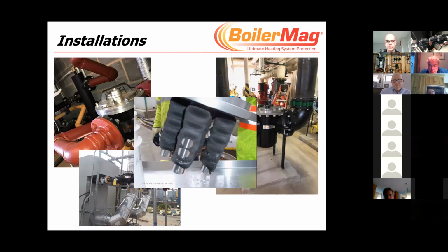We always get the question: how often do you need to clean these? Well, it depends on the system, and how bad the system is. I can give you an example. I installed the BoilerMag on my new boiler system - I'd taken it back to the studs, all new copper piping, no cast iron radiators. I opened mine up after about a month and the magnet was packed. I opened it again after another month and had about half the amount. After about 6 months, I'd hardly got anything at all. So I self-monitored the cleaning frequency, and that's what we'd normally suggest. On an industrial application, we'd probably want to check it after the first day, then after the first week, and see what it's like. You'll develop your own cleaning frequency.